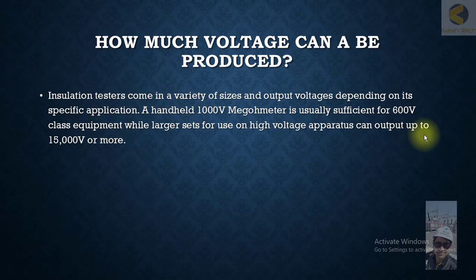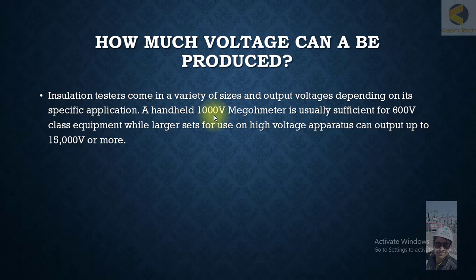For example, if you want to test low voltage cables up to 600 volts, then a 1kV handheld megger — which is basically shaped like a multimeter — will be enough to test the insulation. This is normally used when testing control wiring and control cables; a 1kV handheld will be sufficient.